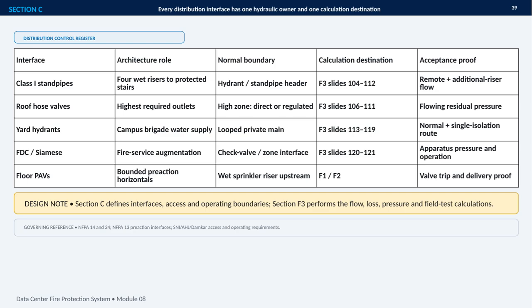Section C defines the interfaces, access, and operating boundaries. Section F3 then performs the hydraulic calculations and field test checks, using NFPA 14 and 24, the NFPA 13 preaction requirements, and applicable SNI, AHJ, and Damkar requirements.